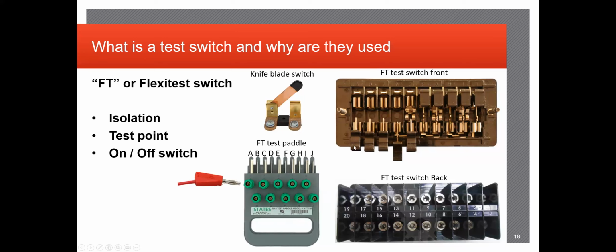Usually it's a 1 or a 0 here. If it's open, it's open. If it's closed, it's closed. Current either goes through or it doesn't. The most common that you'll probably see out in the field is these right up here. These are extremely useful for relay testing purposes, especially because it's easy access for these test paddles to be placed right in. Once you open up all the FTs, you can plug right into these top clamps right here, and plug all your test leads in from your test set straight in, rather than having to use alligator clips or anything else for your testing.